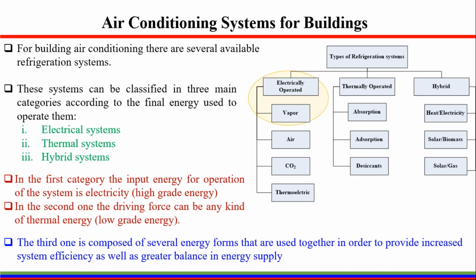Now the current air conditioning systems that are being used by the buildings in the current scenario. We can divide the air conditioning systems into three types: the electrically operated, the thermally operated, and the hybrid. Electrically operated, there can be a vapor compression cycle, and then depending on the other refrigerants, they can be air based, they can be carbon dioxide based, and they can be thermoelectric based.